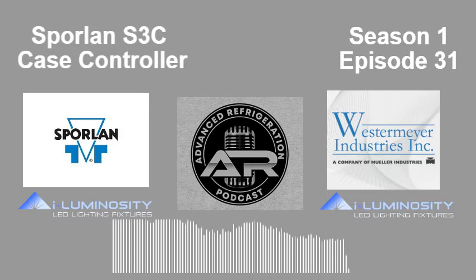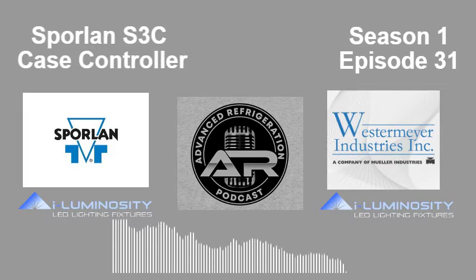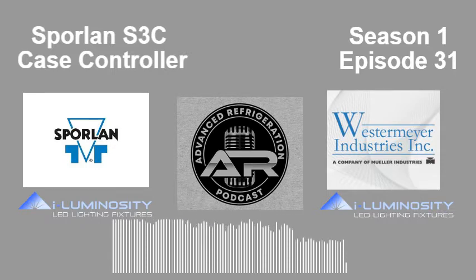So just be mindful of that, guys. If you have a controller that has gone bad because of moisture, and you end up replacing it, the set points are transferred via the actual display module. If you're working with some sort of BMS or BAS system, make sure you write down the IP address on the actual controller, because every single controller has its own IP address, and if it's not right, it will end up not communicating with the BMS.